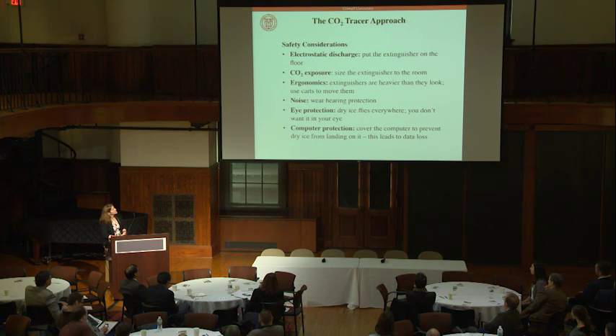Okay, some considerations while we're doing this test: static electricity. When you're releasing, actually emptying the fire extinguisher, there's a lot of static coming out of the horn, and that can hurt your fingers or your feet. CO2 exposure: you've got to keep the levels down. We want to bring it up to a certain point where we can get enough measurement points, but we don't want to have 50,000 ppm of CO2 because that becomes dangerous.